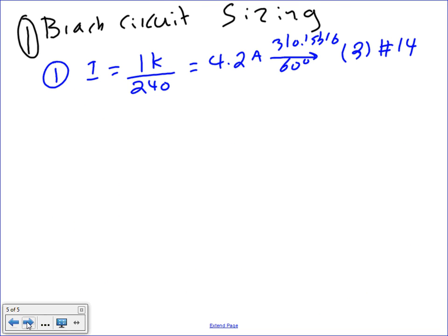All right. From the same calculation, guys, I want to do the overcurrent protection device right away. The smallest overcurrent protection device you can get is what? 15 amp. And this is where this comes from, 240.6. I'm not going to be writing all this stuff, guys, but that's what we're going to be doing for all of them.